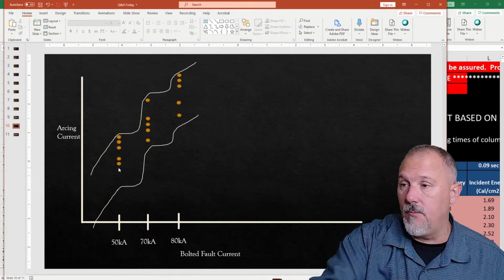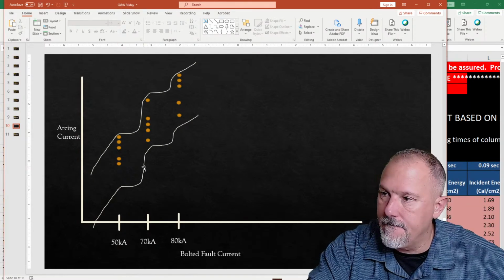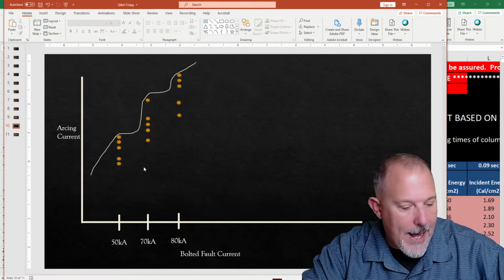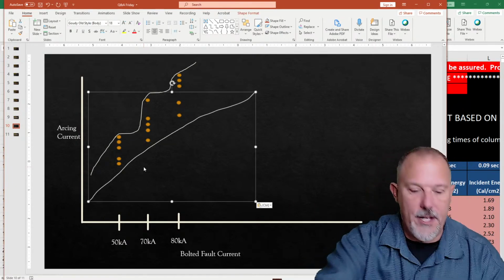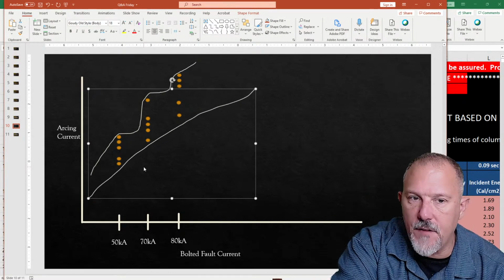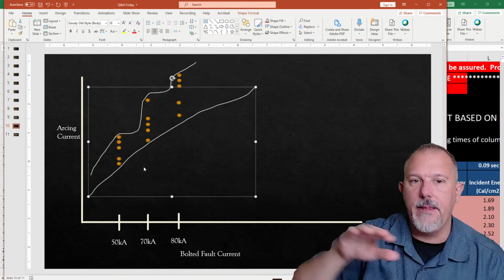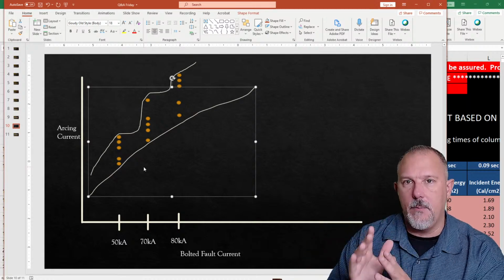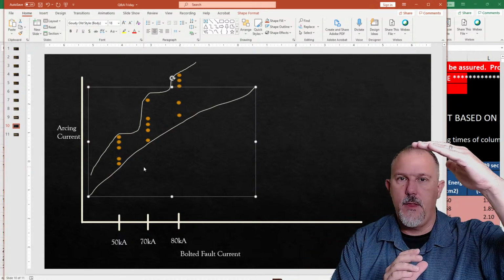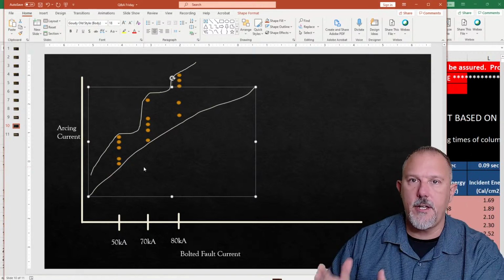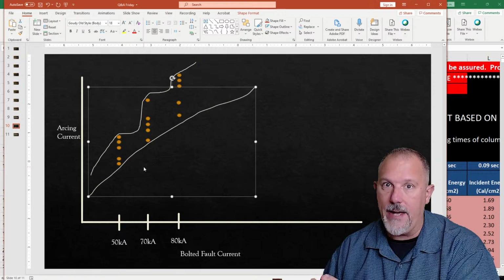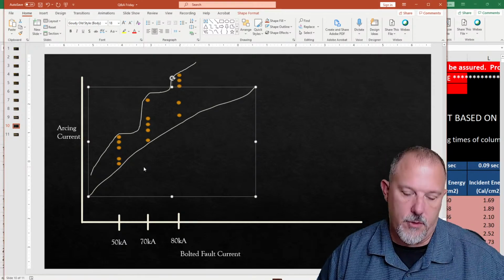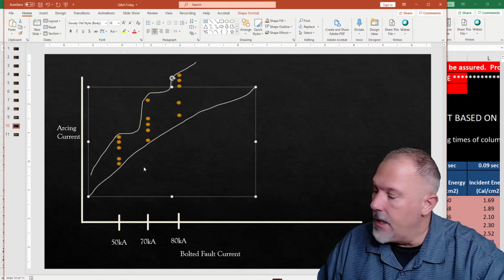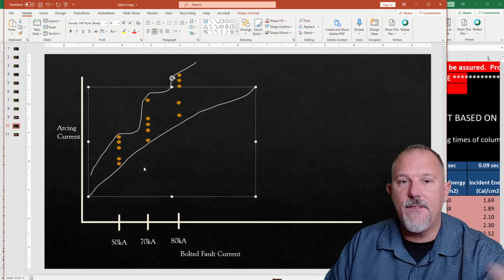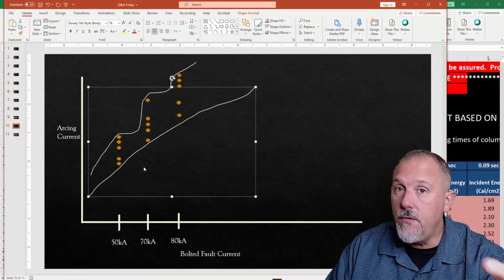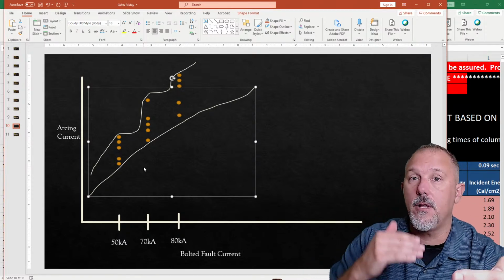So what he did this time was he said, heck with that. We're getting rid of that, and we're actually going to come up with an equation, and we're going to curve fit that equation to give me a line that goes below those bottom data points and encapsulates the maximum and minimum for those arcing currents, because the arcing current could be as low as or as high as for any one of these bolted fault current values. So that tells me that I now have an equation for two values of arcing current, the higher arcing current and the lower arcing current.